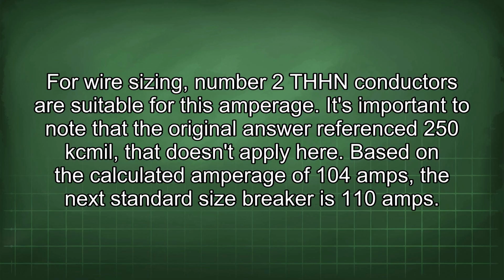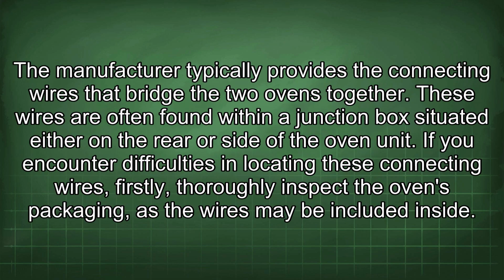It's important to note that the original answer referenced 250 kcmil, which doesn't apply here. Based on the calculated amperage of 104 amps, the next standard size breaker is 110 amps. The manufacturer typically provides the connecting wires that bridge the two ovens together. These wires are often found within a junction box situated either on the rear or side of the oven unit.